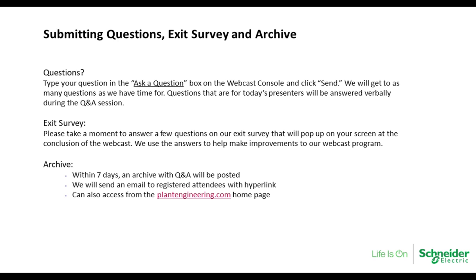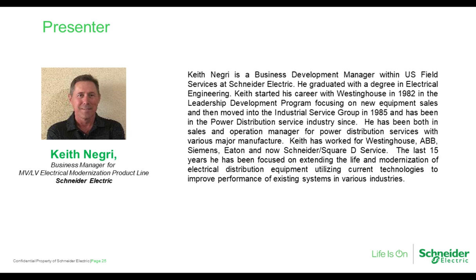Because there are safety factors now involved with old equipment versus new equipment. New equipment has a lot more safety built into it. So yes, we have a group that goes out and does the analyzing and looks at the life expectancy of that gear, and can give you a report back on what we feel that life expectancy is, what condition it's in, and what should be replaced and what shouldn't be replaced. Because not always does everything have to be replaced or upgraded. Sometimes it's fine where it's at, and we'll let you know that too.